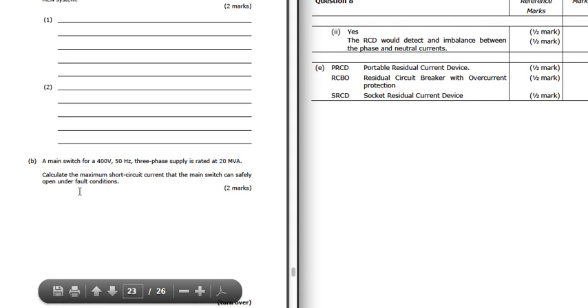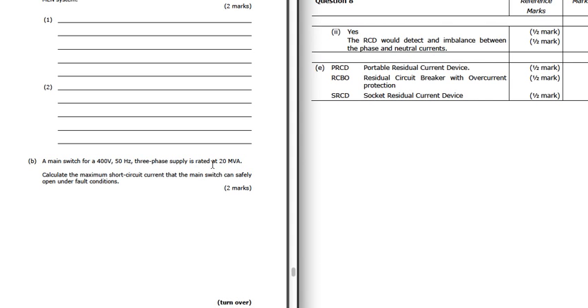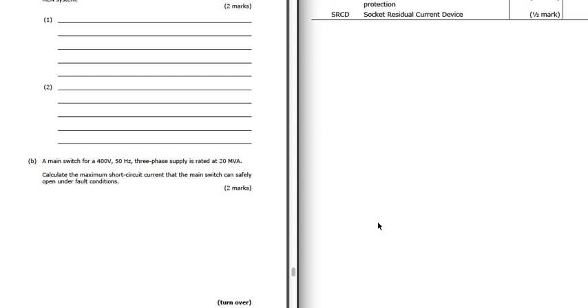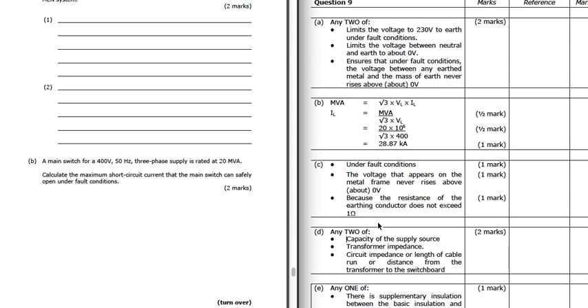A main switch for a 400 volt 50 Hz three phase supply is rated at 20 MVA, mega volt amps. Calculate the maximum short circuit current that the switch can safely open under fault conditions. So we've got an MVA rating. We can work out the current using this formula that VA is √3 VL IL, and we're going to transpose for IL. So IL is going to be the MVA divided by √3 times VL.